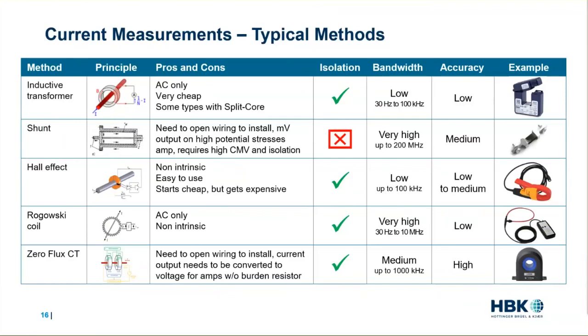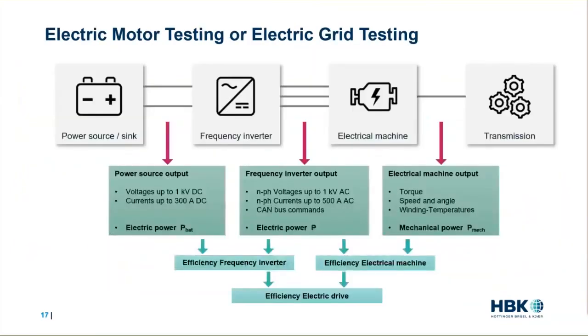Hall effect sensors, often called current clamps, are easy to use and connect. However, they usually offer low bandwidth and low accuracy. Rogowski coils offer high bandwidth measurements and are also easy to use. However, they only offer AC measurements and at a low accuracy. Finally, the best alternative for high accuracy and medium bandwidth is the zero flux CT. It's often used for efficiency measurements in electric motors and drives. And now that we've covered some of the more important terminology, we'll apply what we've covered to some of the more common high power measurement applications we mentioned earlier.